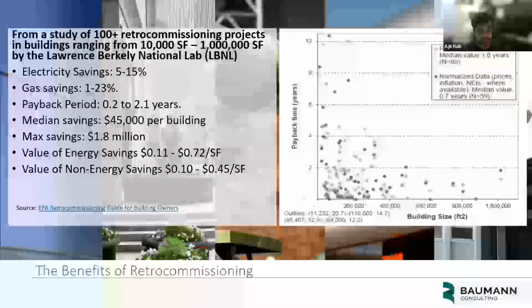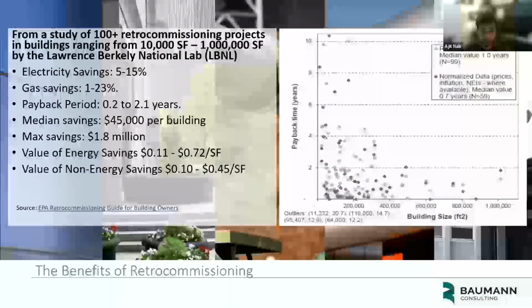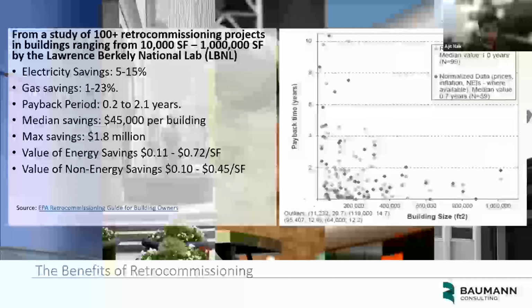The median building saved over $45,000 in operating expenses, and some of the larger buildings saved as much as $1.8 million. They have a pretty complicated methodology for how they value energy and non-energy savings, which I can forward you the information on, but they value these energy savings as about 11 cents to 72 cents per square foot, and the non-energy savings as 10 cents to 45 cents per square foot. The payback was typically lower for smaller buildings, actually. Smaller buildings typically saw faster paybacks and bigger benefits from implementing retro commissioning, but it was effective at buildings of all scales.